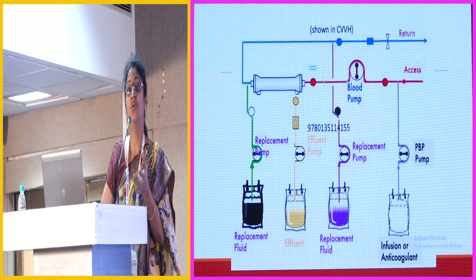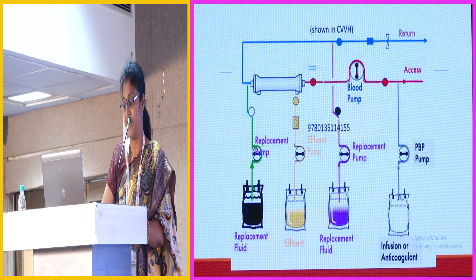I am using the words pull and push, and this is very important to understand. Here the blood is pulled or sucked, so the access pressure is usually a negative pressure. But the pressure after the blood pump is going to be positive, and the TMP as well as the return pressure or outflow pressure are all going to be positive. When we have 2 different pressures, obviously there will be a pressure difference, so we have a monitor to note this difference. This is also important because in CRRT we have an effluent pump. Here also we are trying to generate positive pressure to get the ultrafiltration, except in CVVH mode where it will be a negative pressure to draw the ultrafiltration. So here also we have a pressure.